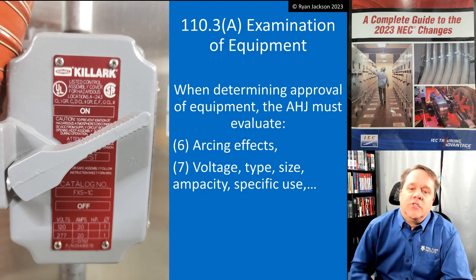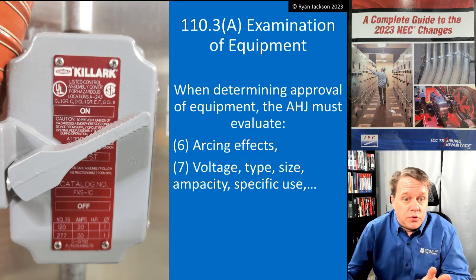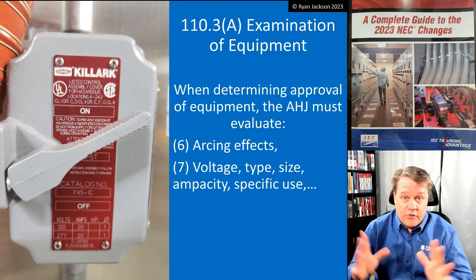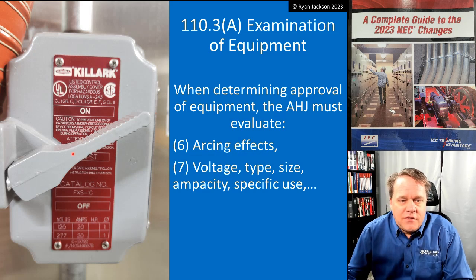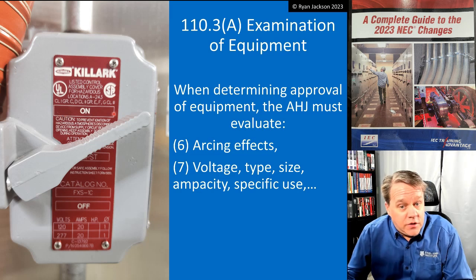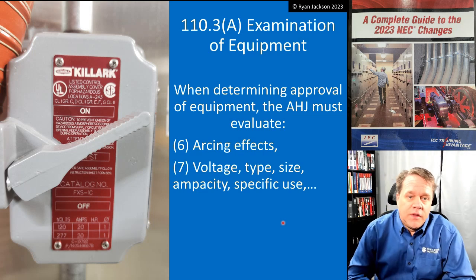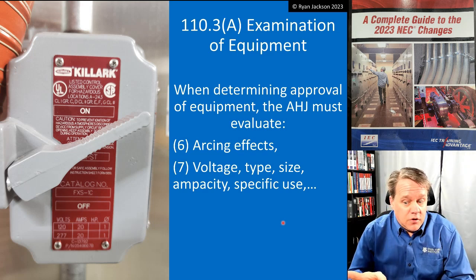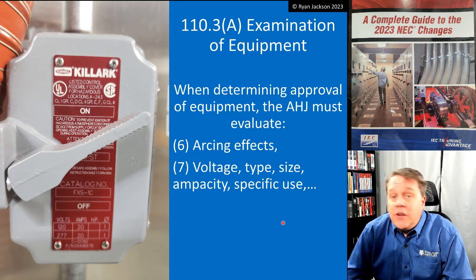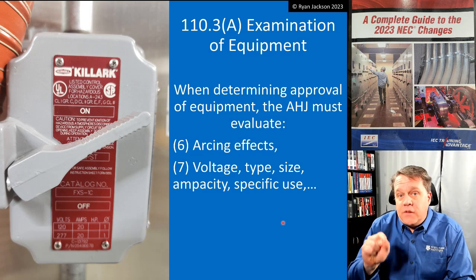We also have to look at arcing effects and consider voltage type, size, ampacity, and specific use. Here's an explosion-proof and dust-ignition-proof switch enclosure. It says it's suitable in Class I Groups C and D, Class II Groups E, F, and G, and Class III. Class I contains Groups A, B, C, and D — but this is only rated for Groups C and D. What if you're installing in an area hazardous due to acetylene or hydrogen — Group A or Group B? Can't use it. We need to evaluate specific use and understand the product's limitations.